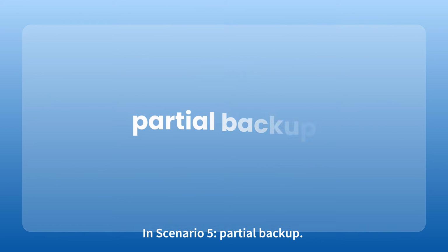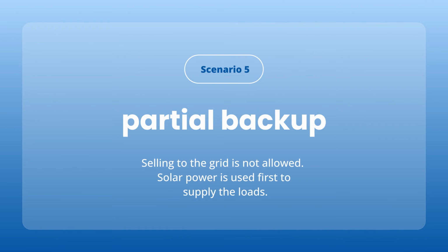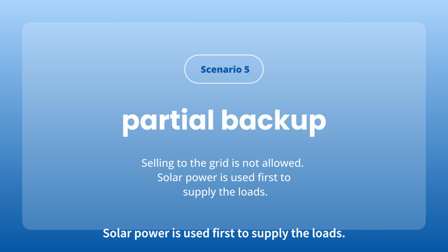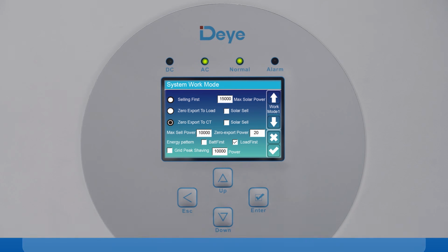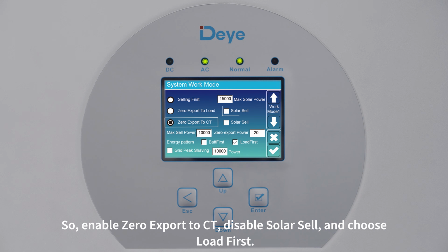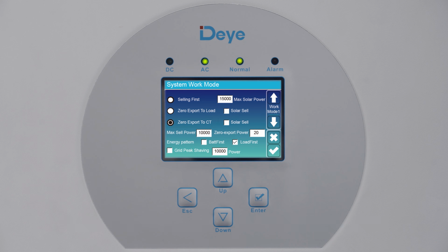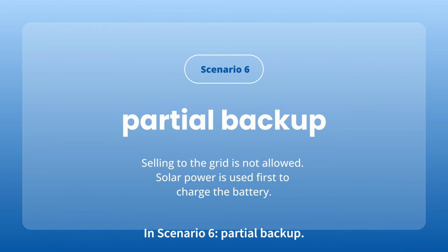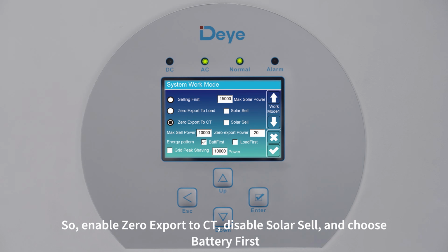In scenario 5, partial backup. Selling to the grid is not allowed. Solar power is used first to supply the loads. So, enable zero export to CT, disable solar sell, and choose load first. In scenario 6, partial backup. Selling to the grid is not allowed. Solar power is used first to charge the battery. So, enable zero export to CT, disable solar sell, and choose battery first.